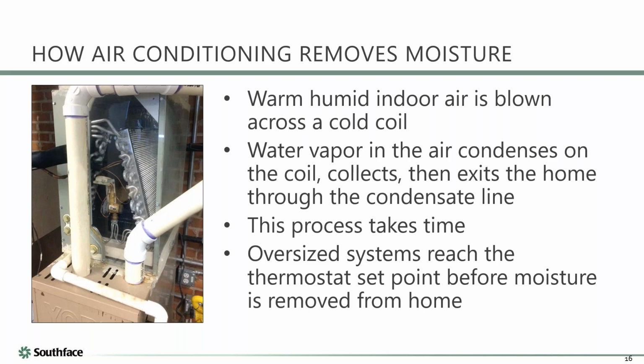So when it operates, the warm, humid air from the house is blown across the fins, and it comes out colder. The thicker the coil, the more fins, the more surface area you have, to not only cool air but also have condensate occur. The drops of condensate hit each other and drip down into a pan at the bottom. After a certain amount of time, the liquid level rises enough, and it flows out this little PVC pipe, which is the condensate line. The important thing here, and Joey, maybe you can elaborate on this, is that the system has to run a long time in order to remove condensate.